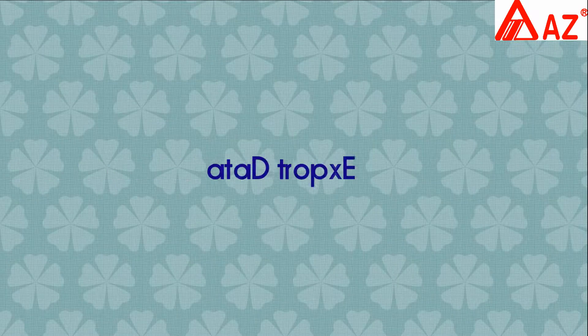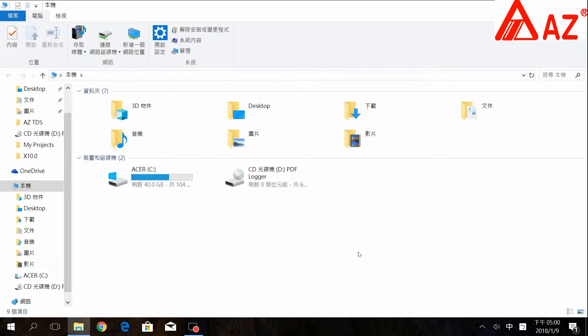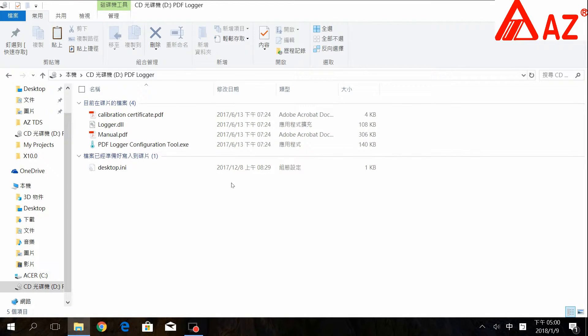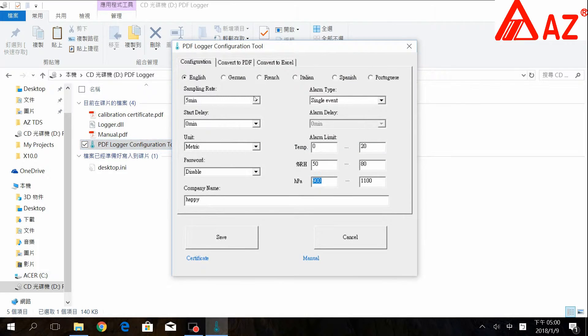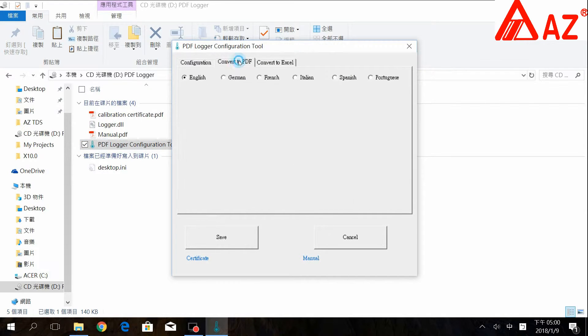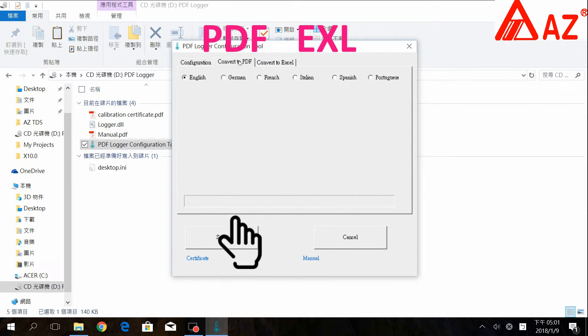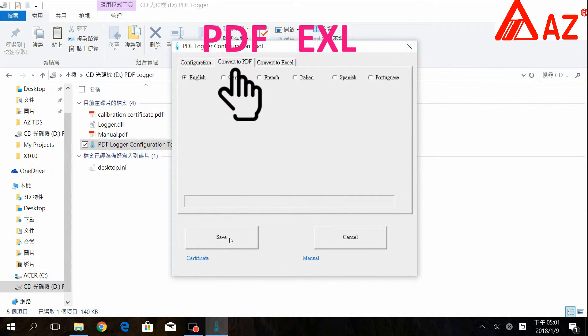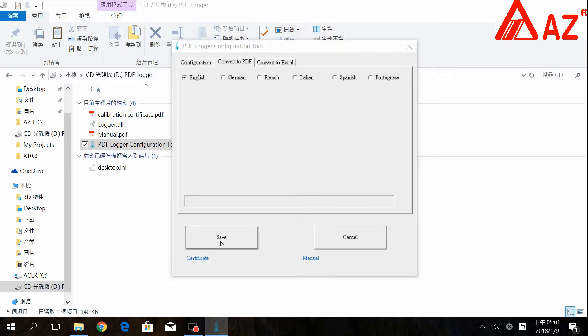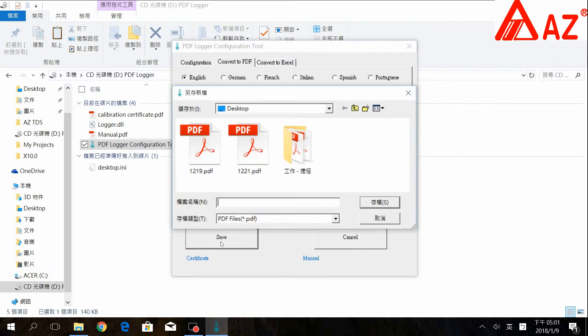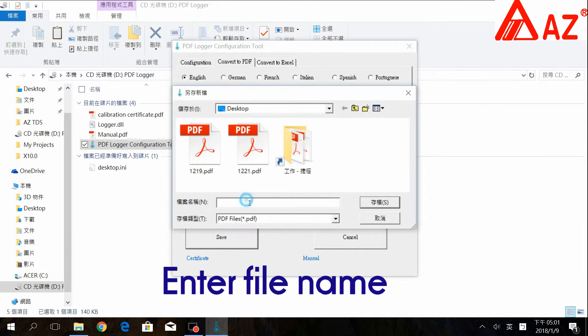Export data: long press stop to stop logging, or plugging the logger into the USB port will also stop logging. Open the same file, choose PDF or Excel report format, then select the location and enter the file name to save the generated report.